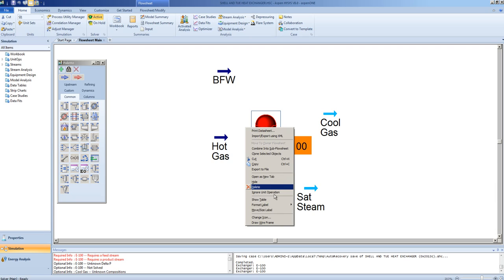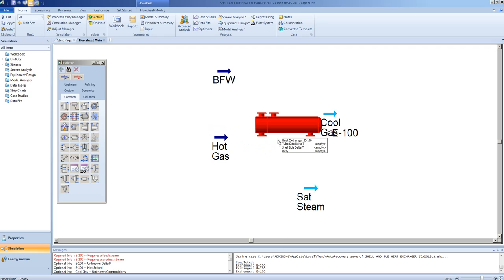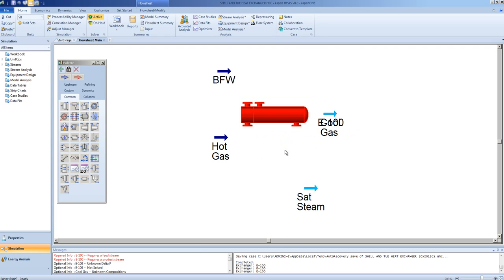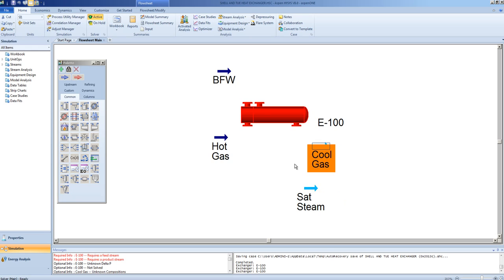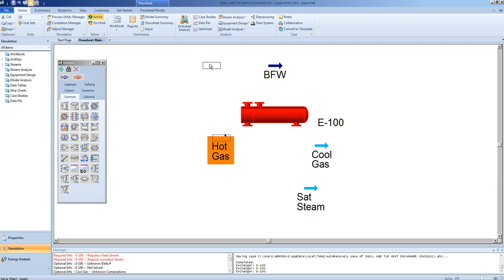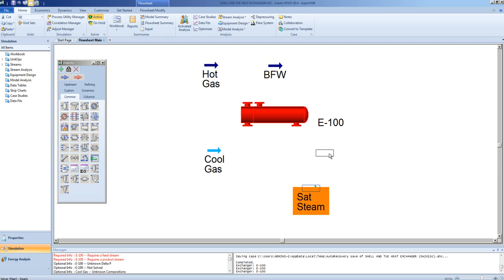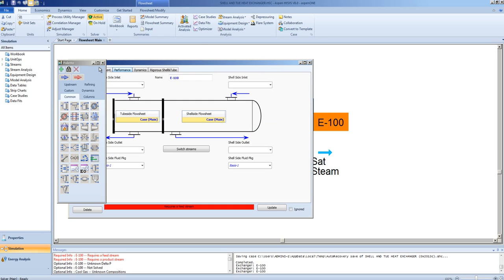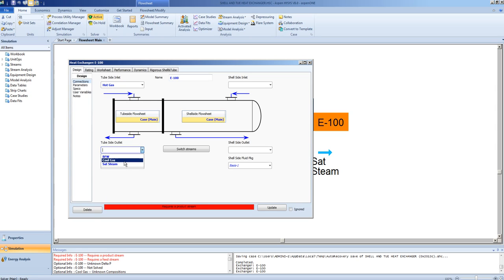You can exchange the icon and choose an icon that best suits your needs. In this case, the boiler feed water will be fed to the shell side. The hot gas will be on the tube side. The tube side inlet will be the hot gas. The tube side outlet we will specify as cool gas.